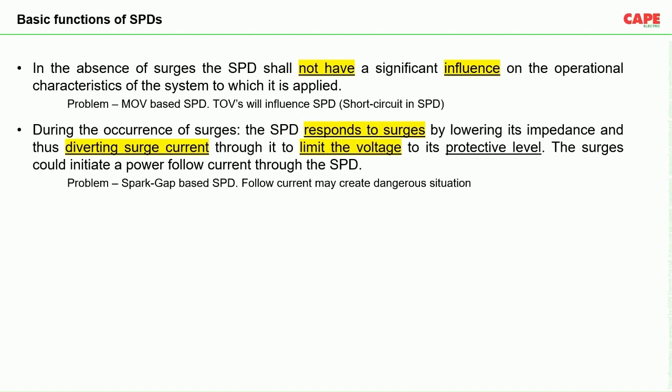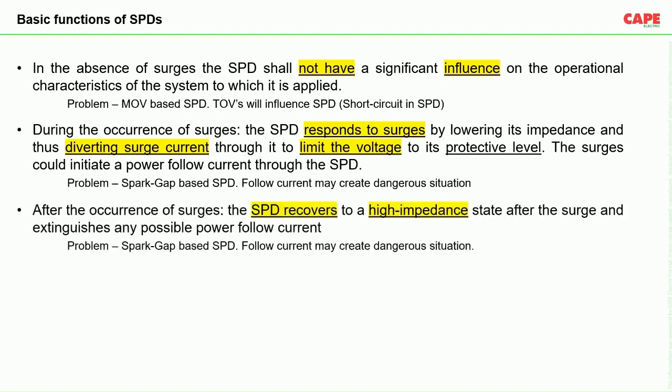In the case of spark-gap-based SPDs, there can be an issue of follow current, which can create a very dangerous situation — that will be discussed later. The third function: after the occurrence of surges, the SPD recovers to a high impedance state and extinguishes any possible follow current. Once the surge is gone, SPD should return to its normal high-impedance state and not create any follow current. In the case of spark gaps, follow current can create a dangerous situation.